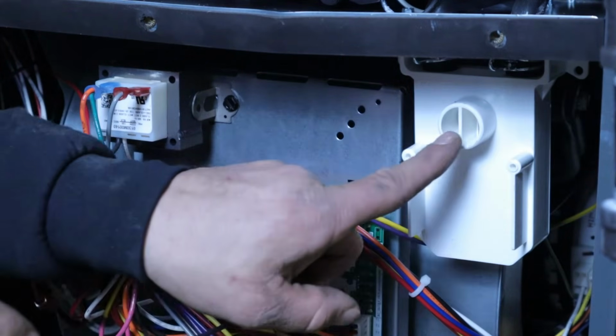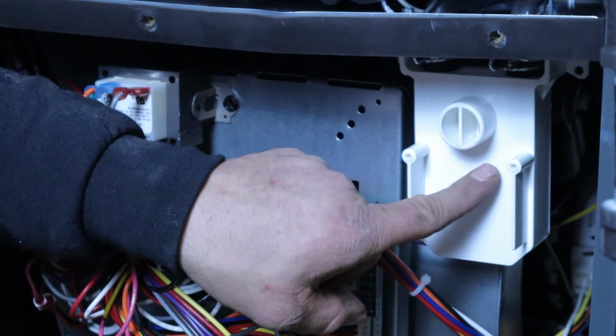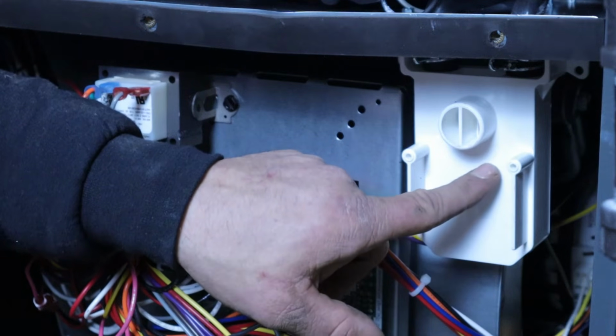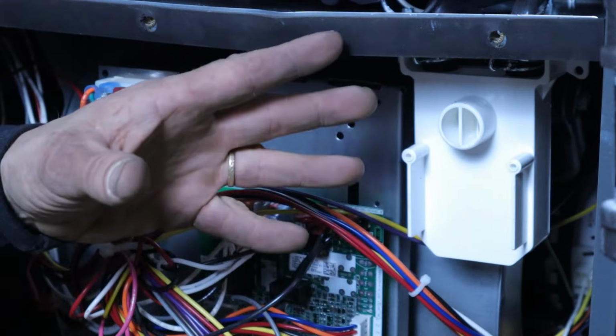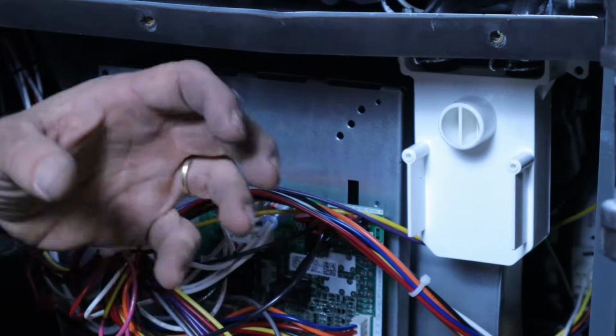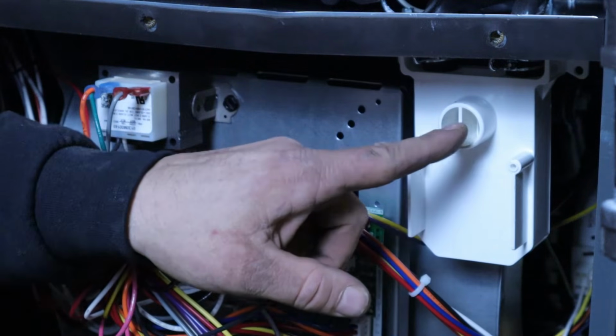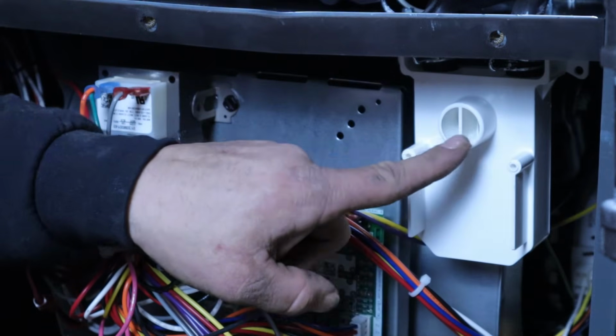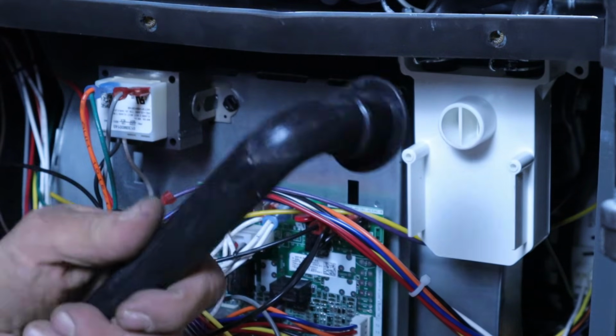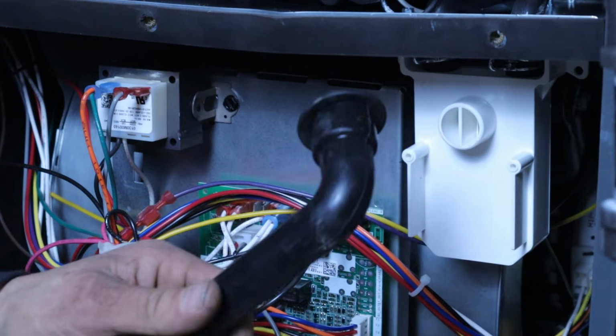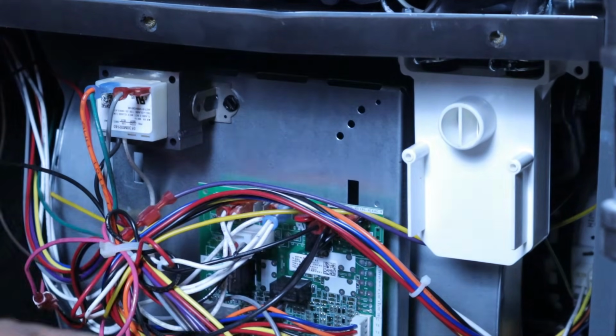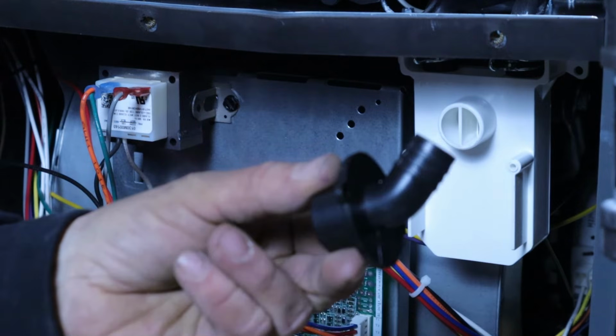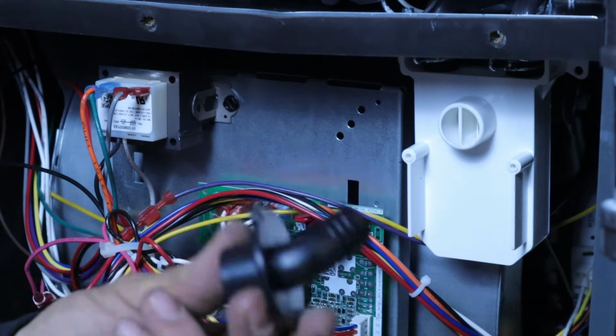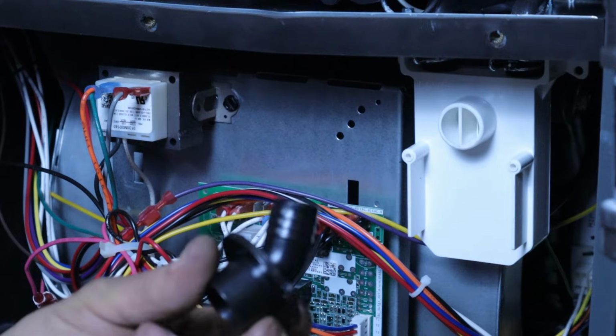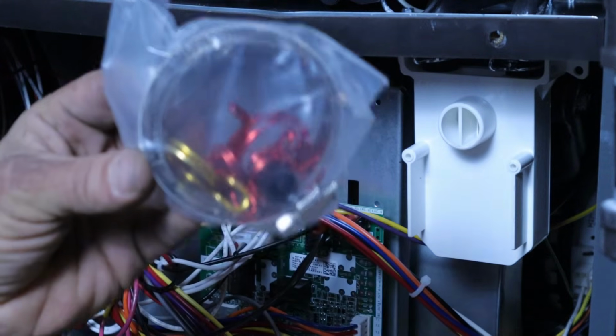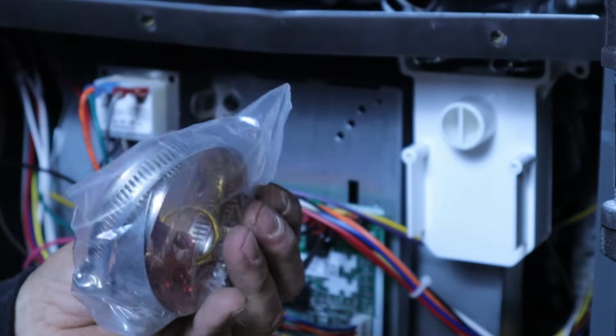We're going to hook that up to, this is our trap for the condensate that comes out of our secondary heat exchanger. So when the furnace is running and the heat goes through the secondary heat exchanger, it cools it down so much it condenses and we actually get water. So this trap is where our water's coming out on our 90% furnace. We're going to hook this hose up and run it outside the furnace into a condensate pump. We're also going to use this little fitting that comes with the furnace inside that bag. And this is where we're going to hook the hose up and connect it to the side of the furnace where we're draining out. And we have a bag with a bunch of hose clamps on it. And we're going to be using 2 of those.